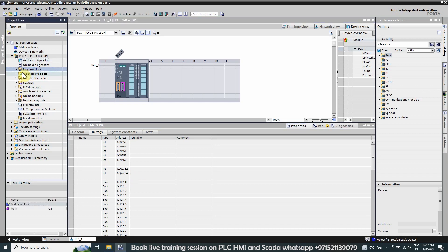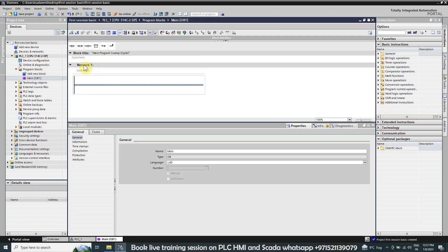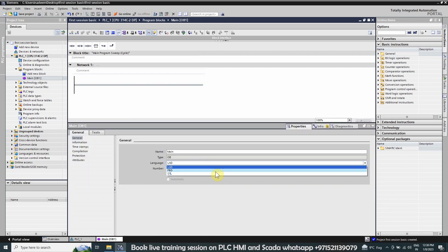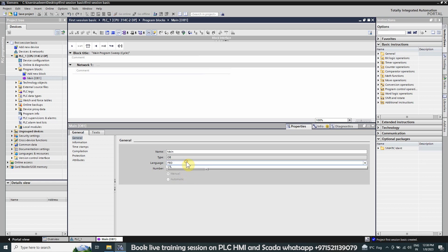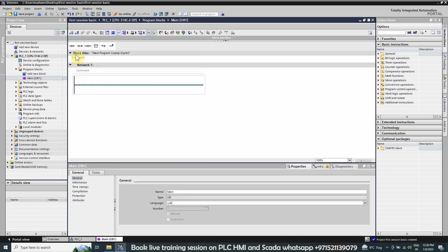To make a program, we will go to Program Blocks, expand this folder, and double click on OB1 — Organization Block 1 — which is the main block added by default into any CPU. We can see that Network 1 is already there. We can change the programming language for this block; options include Ladder, Function Block Diagram, and STL. For today we will select Ladder Diagram and insert a NO contact.